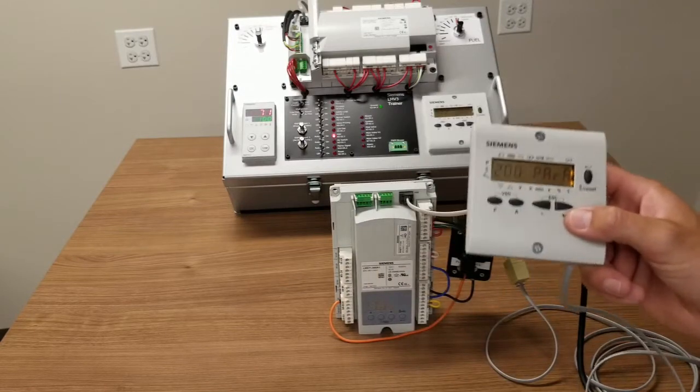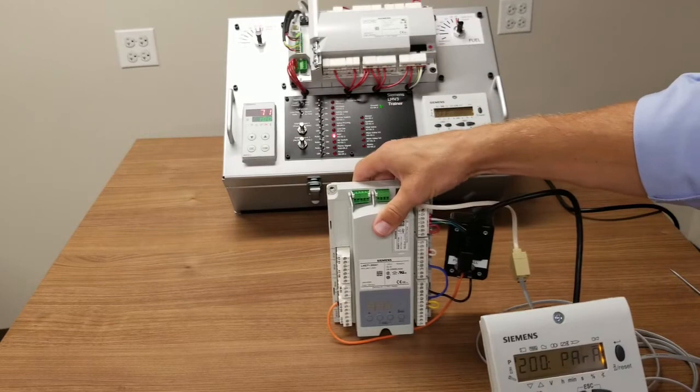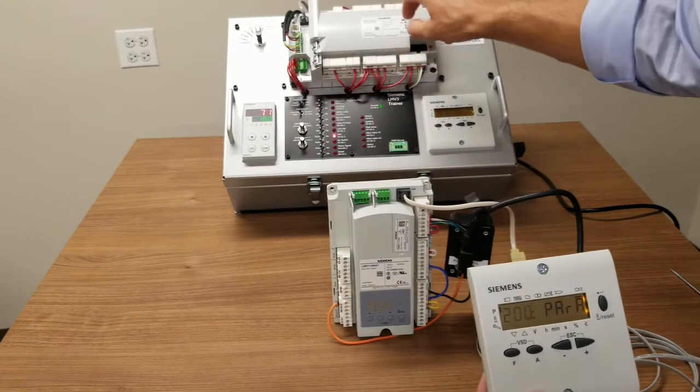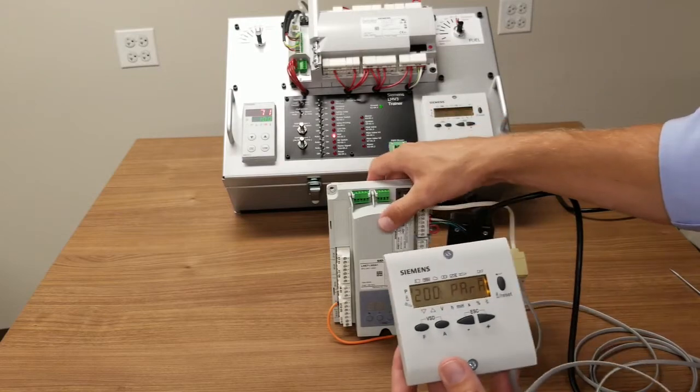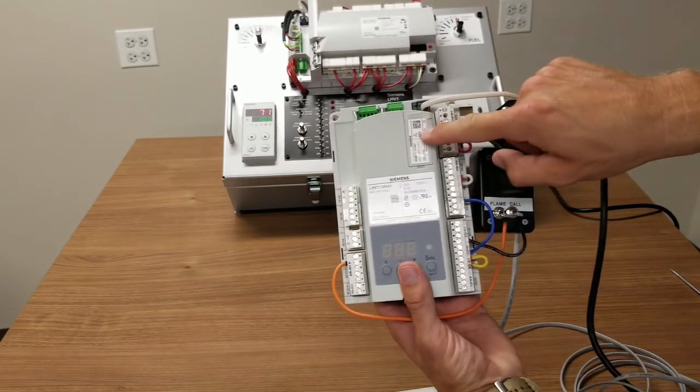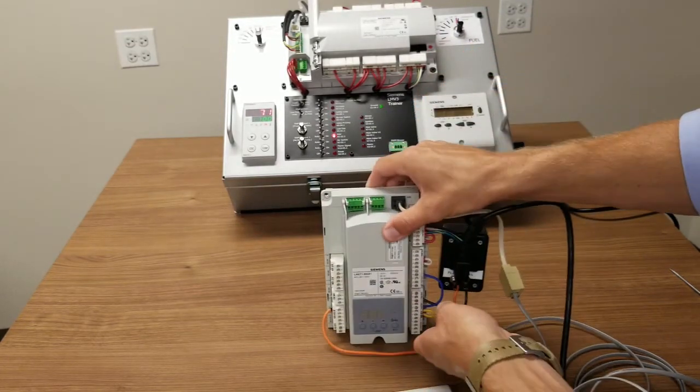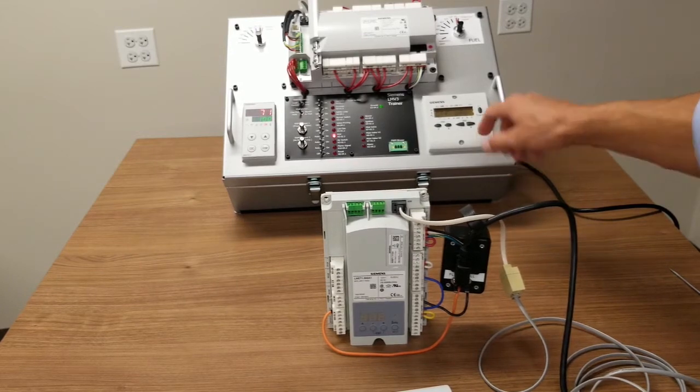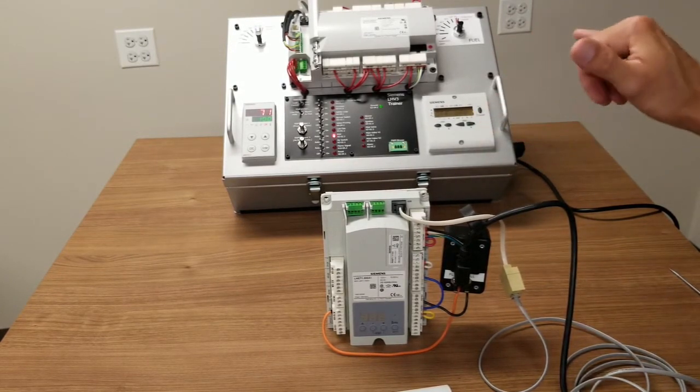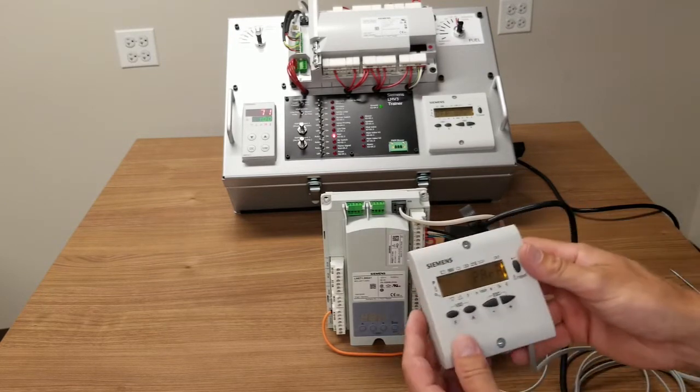Now, the changes you've made have taken place in the control themselves, in the LME, or in the case of the LMV3, in the LMV3. It's wise to back them up. And in the case of the LME, you'll back them up to this program module so that if something happens down the road, your settings will be saved. In the case of the LMV3, you'll back them up to the AZL itself. In both situations, it's a real benefit should something happen to the control down the road.